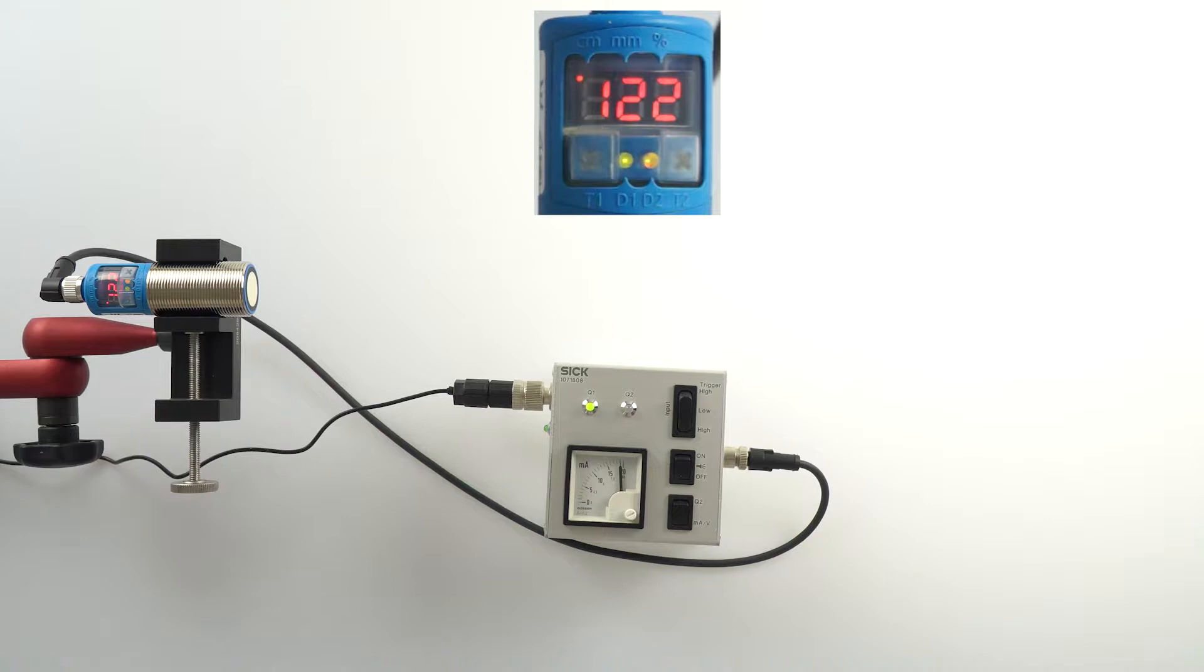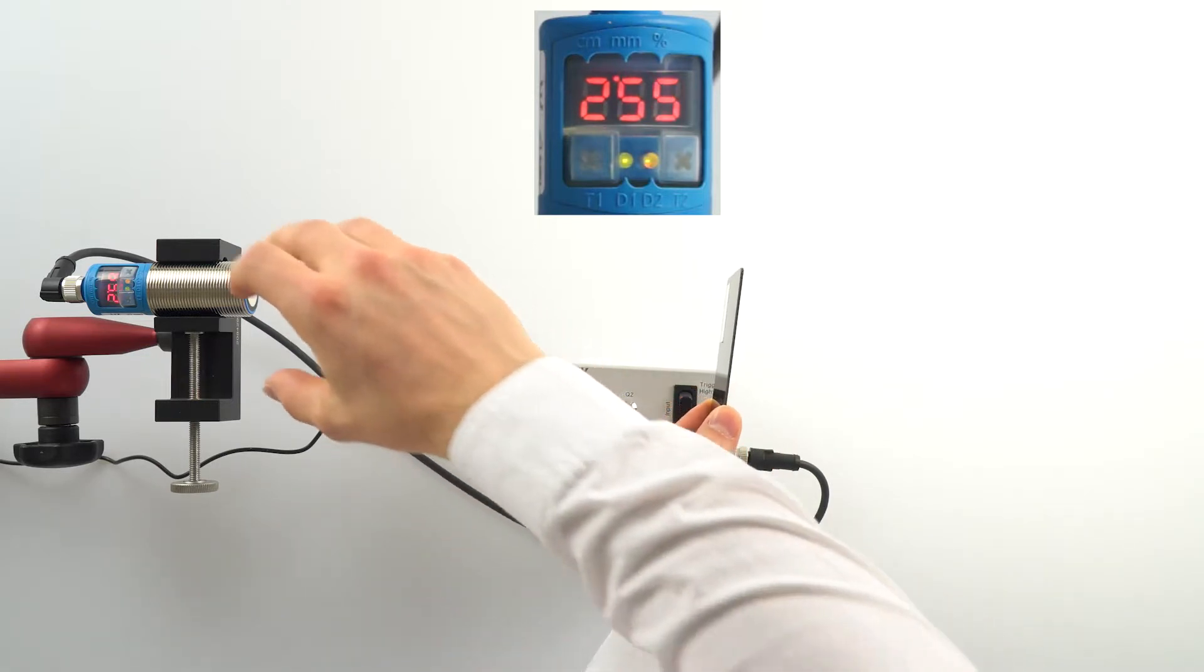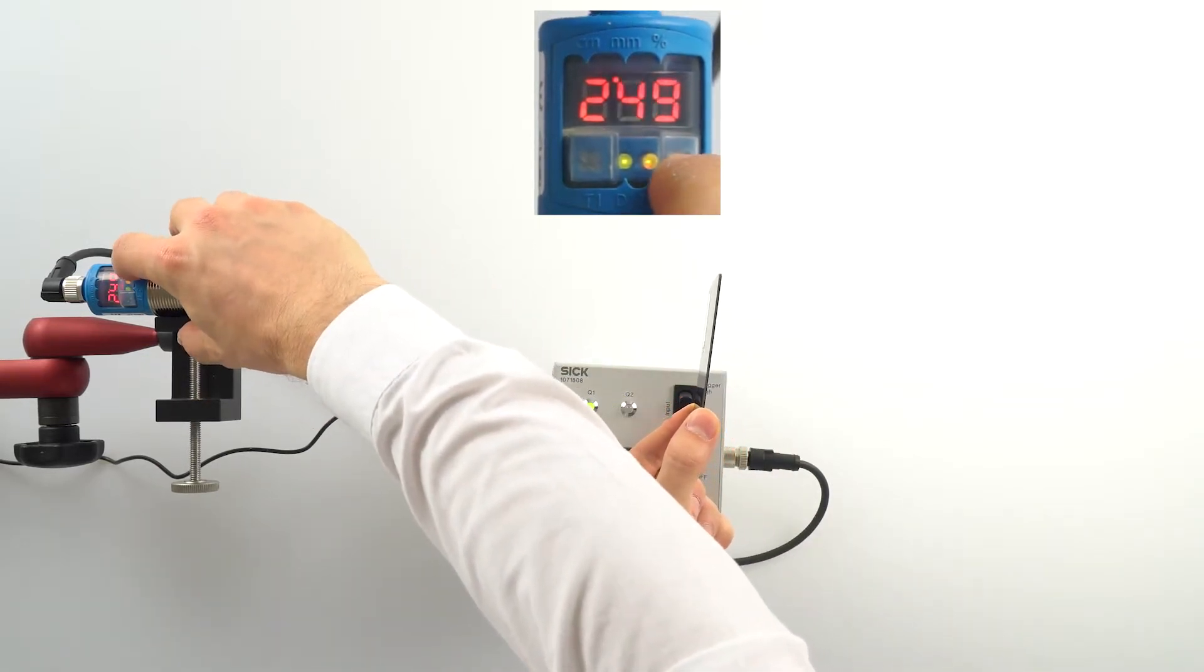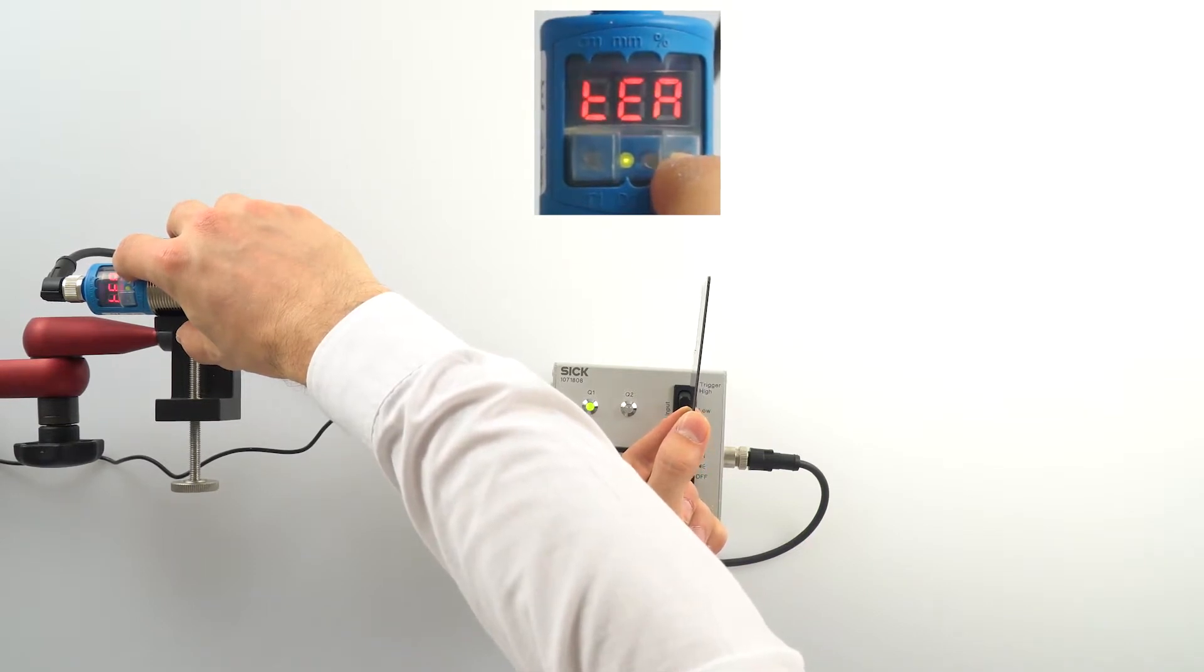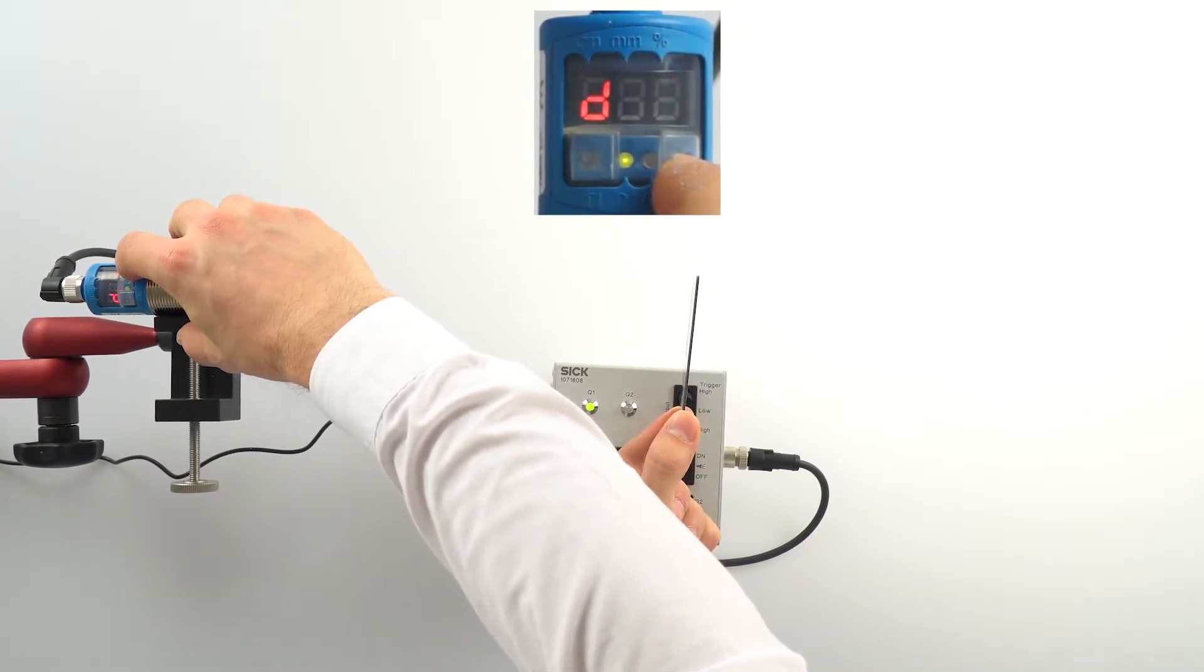Position any ultrasonic reflecting object, such as a business card, in front of the sensor at the desired distance for the limit switching point. Then press the T2 key until D appears in the display. The sensor is then showing the current measurement value.